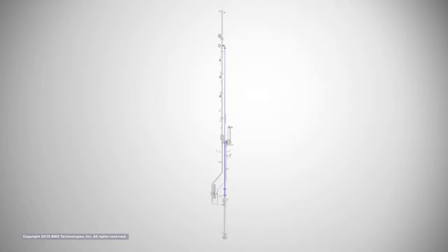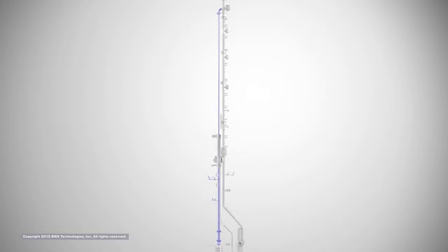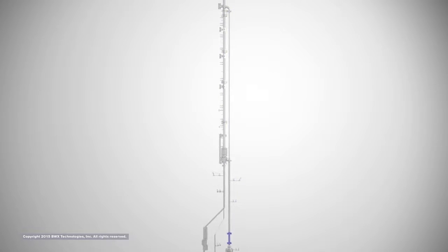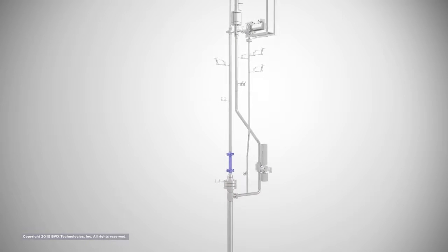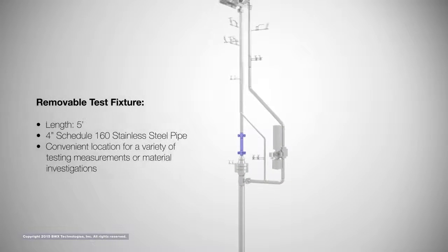The core heaters create a symmetrical cosine axial heater profile with an adjustable radial profile using four groups of core heaters. Within the reactor vessel, beyond the core unit, coolant flows through a riser section that carries flow to the inlet to the steam generator. Along this section is a removable spool piece accommodating process scale flow field study.